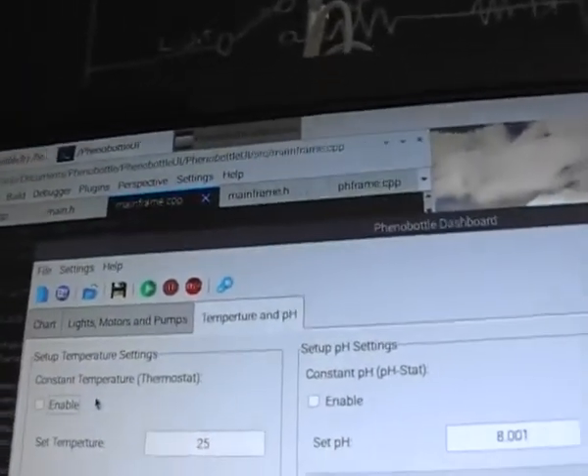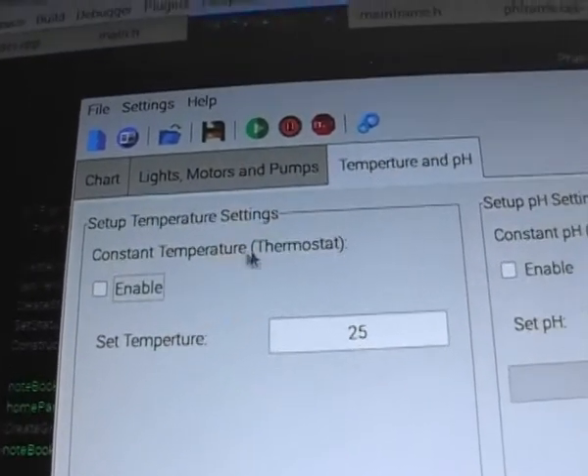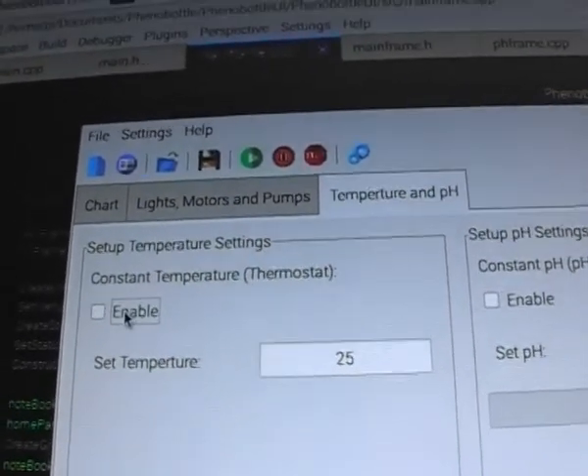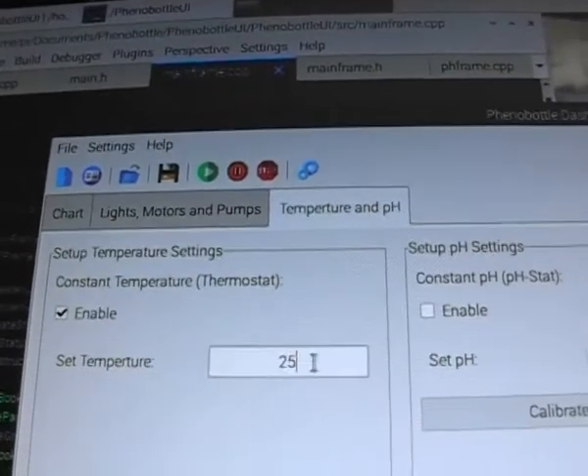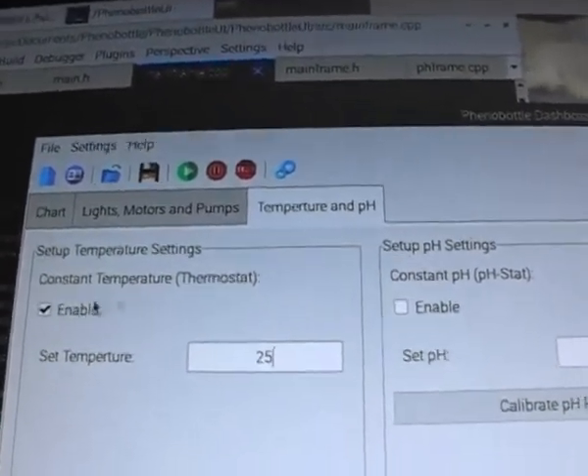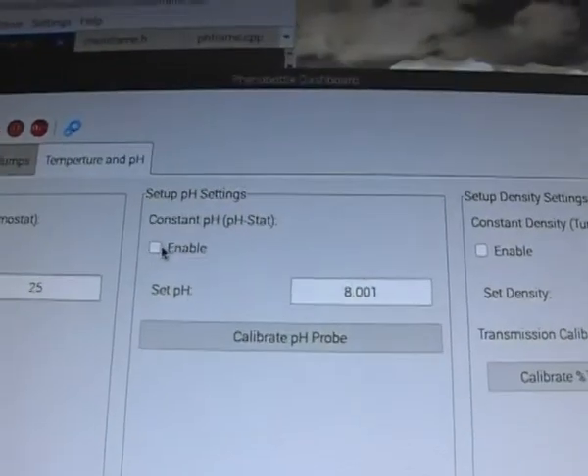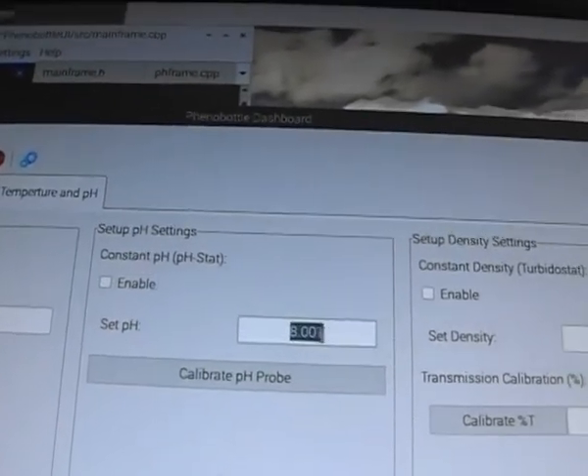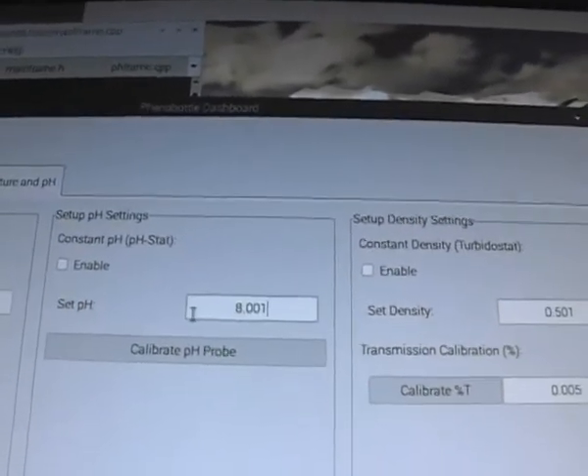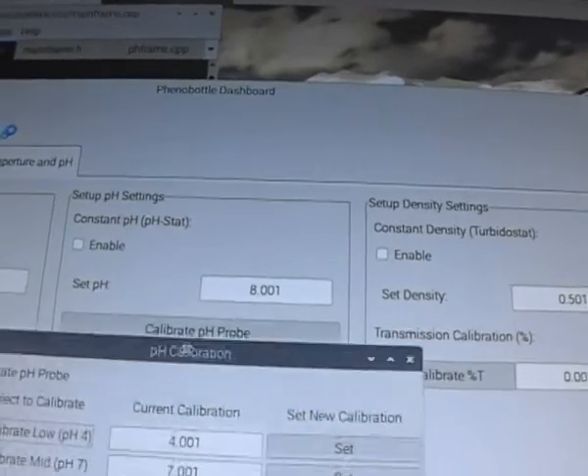In terms of environmental controls, we're looking at temperature, pH and density settings. Here we can set up a constant temperature, like a thermostat mode. You enable it, and you set whatever temperature you want the culture to be at. The same goes for the pH, which you can just enable at whatever pH you want to run at. We also have a calibration interface for the pH probe.